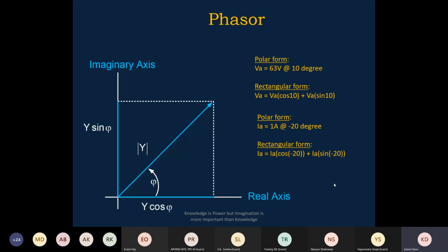Sometimes I see mistakes where people's interpretation itself is wrong during fault injection testing. What they are injecting, whether the values are written in polar form or rectangular form, they do the wrong injection and then see the relay simulations. That is a practical thing I have seen. So specifically we need to understand whether the data shown in the software is polar or rectangular form. If it is rectangular, convert it into polar form, and then you can inject. That will be much easier. For example, you are injecting 63 volt at the rate 10 degree, something like that.